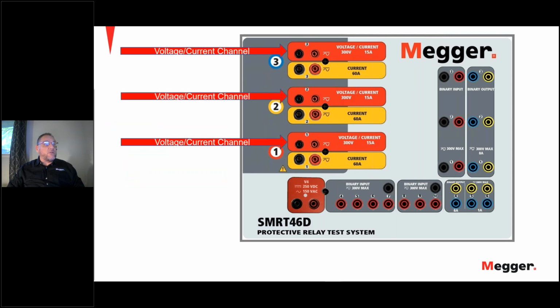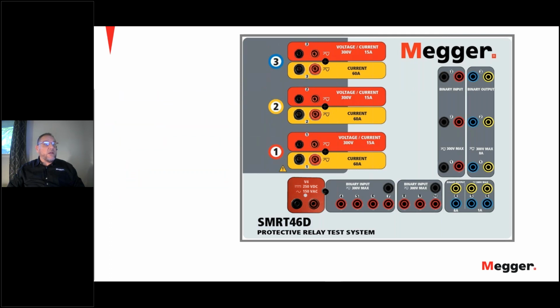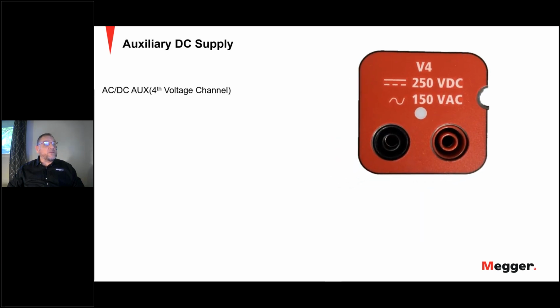We've got the 3 voltage channels, the 3 current channels, and we've got a voltage or battery simulator. Now, just as a note again, not all of the units have the same battery simulators. Some of the units only have a DC supply, whereas some of the units will have the 4th voltage, which is the 0 to 150 volt AC, as well as the up to 250 volt DC. So this is the typical unit, which is the 4th channel.